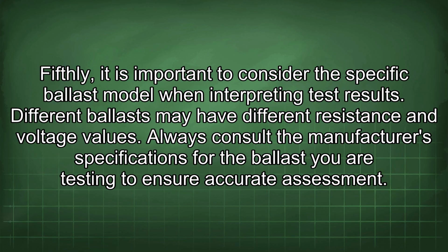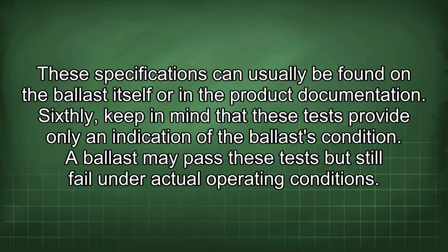Fifthly, it is important to consider the specific ballast model when interpreting test results. Different ballasts may have different resistance and voltage values. Always consult the manufacturer's specifications for the ballast you are testing to ensure accurate assessment. These specifications can usually be found on the ballast itself or in the product documentation.